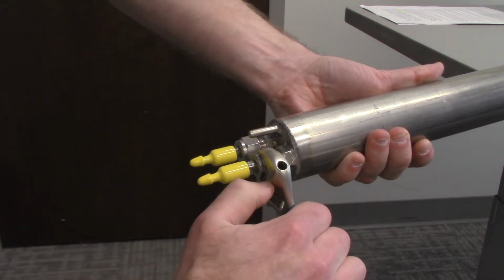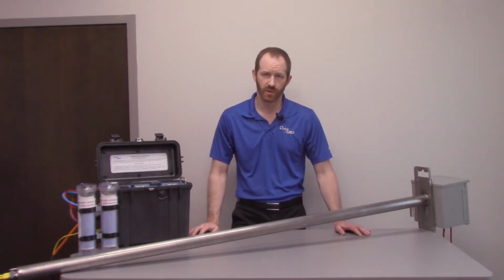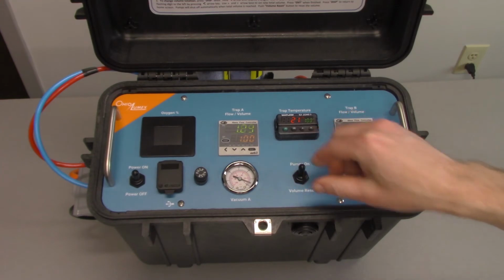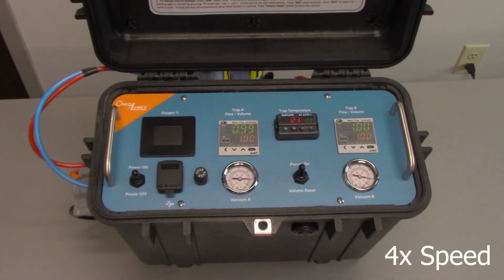There's one more thing you need to do before inserting the probe into the sample gas, and that's to perform a leak check. This is straightforward. With the sorbent trap caps in place, turn the pumps on and wait for the sampling trains to be evacuated.